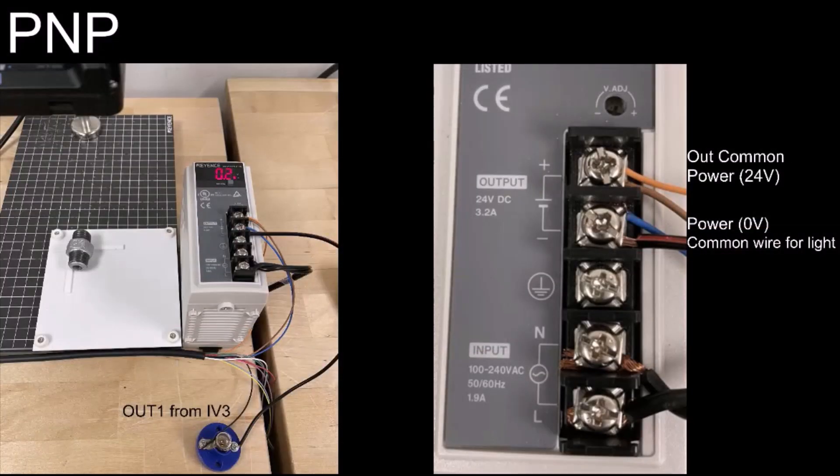In this example, I'm going to start with a PNP setup. On the left-hand picture, you can see my black output 1 wire is going to a light. On the picture on the right, you can see that I have my brown wire for 24 volts and my output common connected to my 24-volt terminal of the power supply. Right below that, in Terminal 2, you can see I have my blue wire and my common for the light connected to my 0-volt terminal of the power supply.